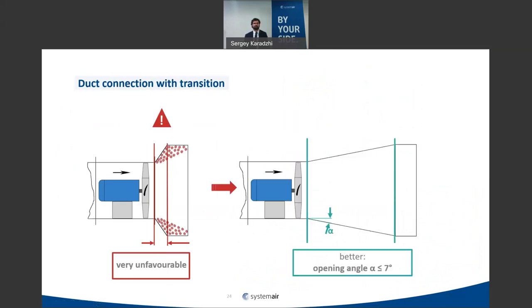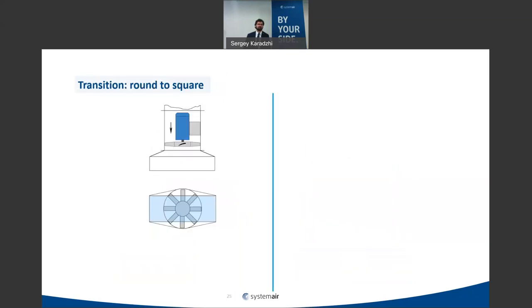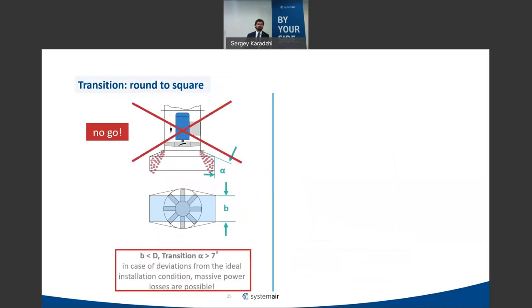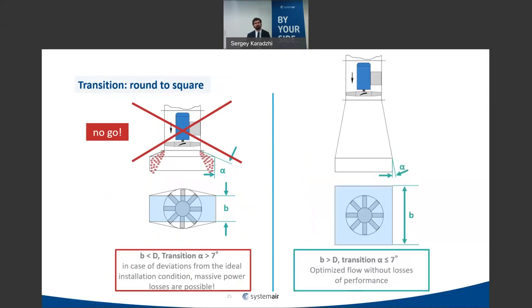It's always better to install a fan with a diffuser having an opening angle of about 7 degrees. The losses in a diffuser as a function of opening angle can be checked in technical books. The same applies for a round-to-square transition: use an opening angle of about 7 degrees and ensure the square cross-section is larger than the fan diameter. Smaller squares are not recommended.